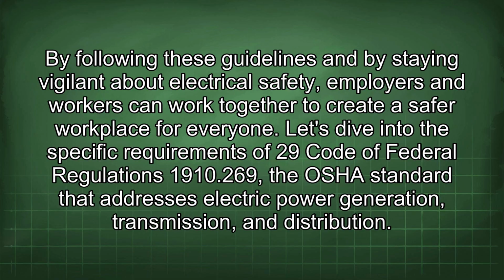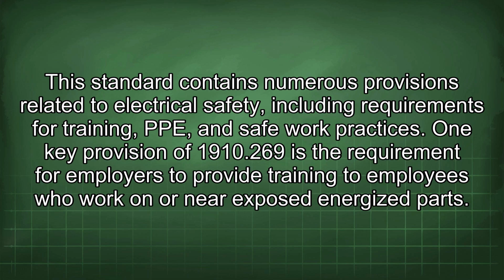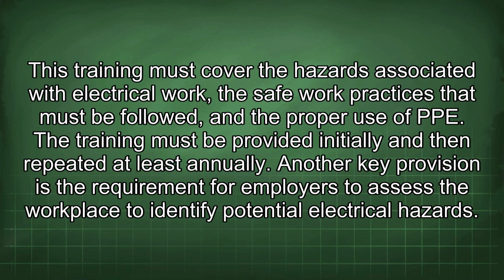By following these guidelines and by staying vigilant about electrical safety, employers and workers can work together to create a safer workplace for everyone. Let's dive into the specific requirements of 29 Code of Federal Regulations 1910.269, the OSHA standard that addresses electric power generation, transmission, and distribution. This standard contains numerous provisions related to electrical safety, including requirements for training, PPE, and safe work practices. One key provision of 1910.269 is the requirement for employers to provide training to employees who work on or near exposed energized parts. This training must cover the hazards associated with electrical work, the safe work practices that must be followed, and the proper use of PPE. The training must be provided initially and then repeated at least annually.